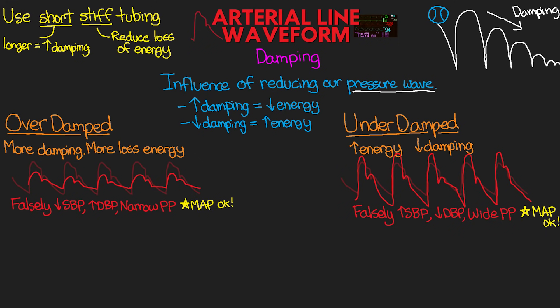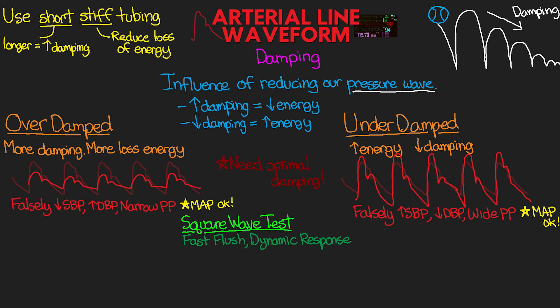That was a lot to unpack with damping — it's definitely not something we normally think about in critical care, but it definitely will have an effect on our A-line and its accuracy. That leads right into something called the square wave test. Now that we know our pressure tracing can be inaccurate due to damping, what we need is what we refer to as optimal damping of our waveform. Knowing this waveform is accurate is imperative, as some treatment options will depend on the accuracy of these numbers. Fortunately, we have a very easy test to check the dampening of our system — the square wave test. You may also hear it referred to as the fast flush or the dynamic response test, but they are all the same thing.